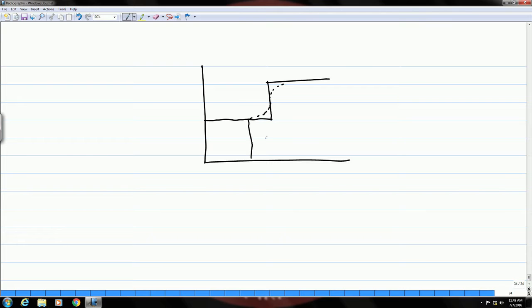Okay, so, that means you had this boundary where there was a 90-degree change, but when you see the image you do not see that sudden change, rather it comes out as a gradual change. Okay. So, this inability to reproduce this boundary properly, as we defined just now, is known as the unsharpness of the image. Okay. And this primarily happens due to the focal spot size of the machine.